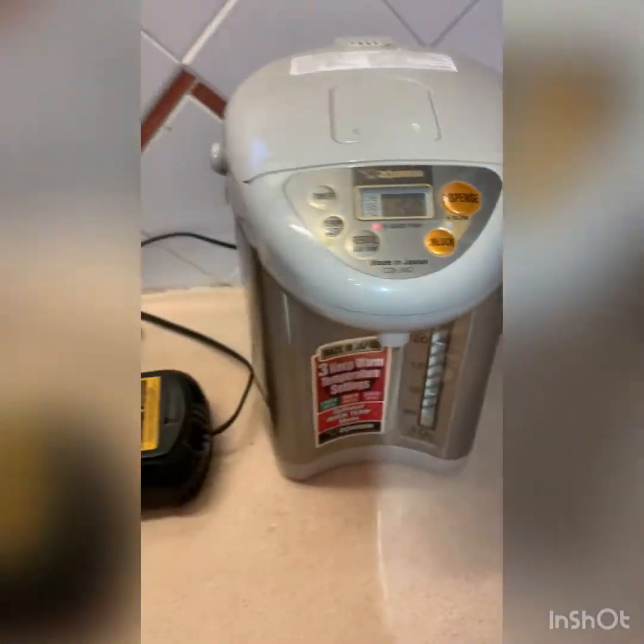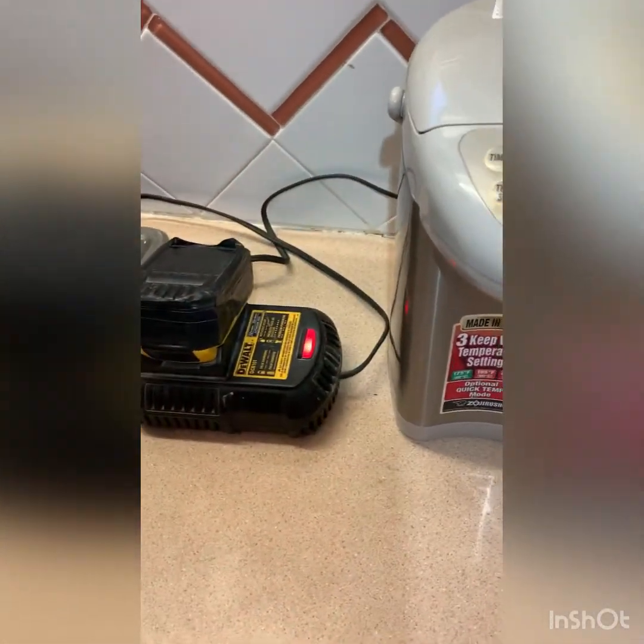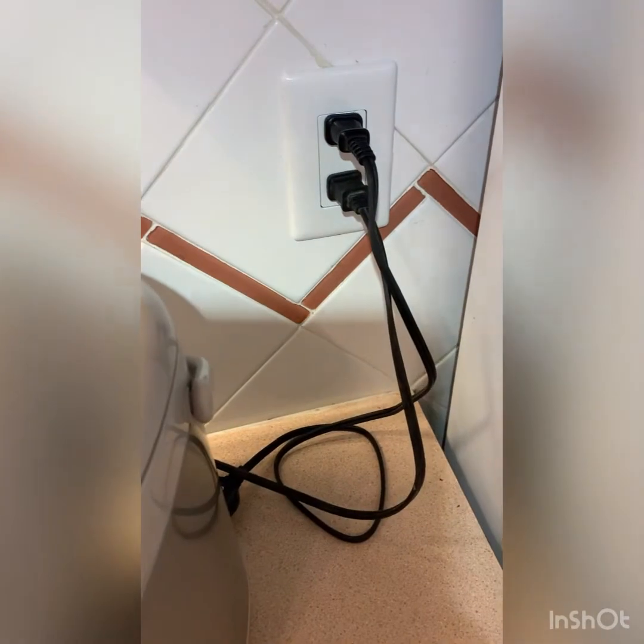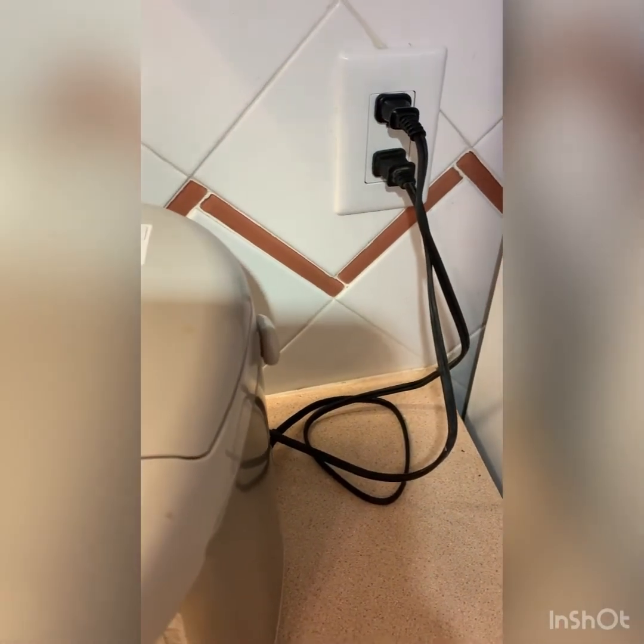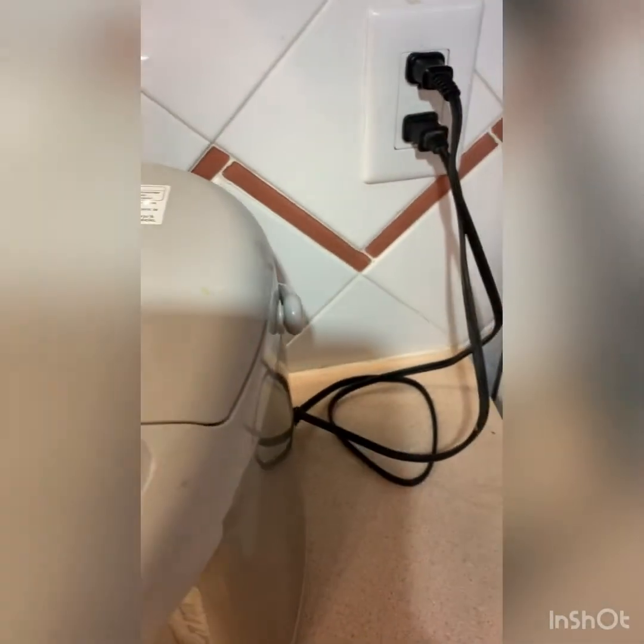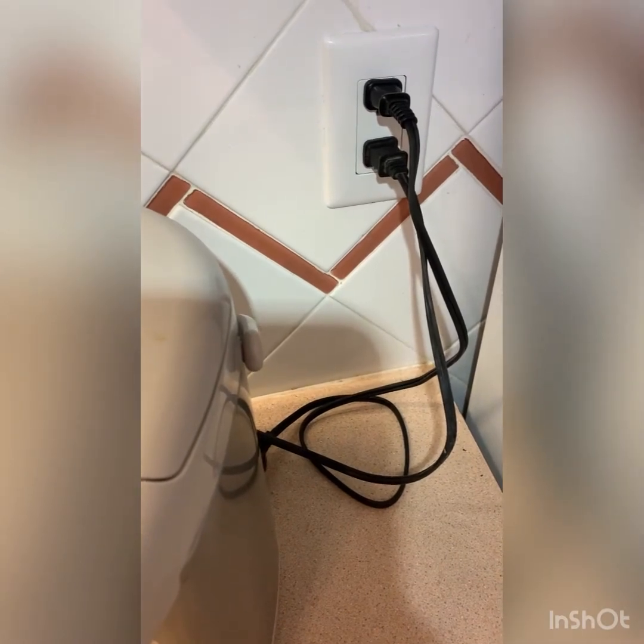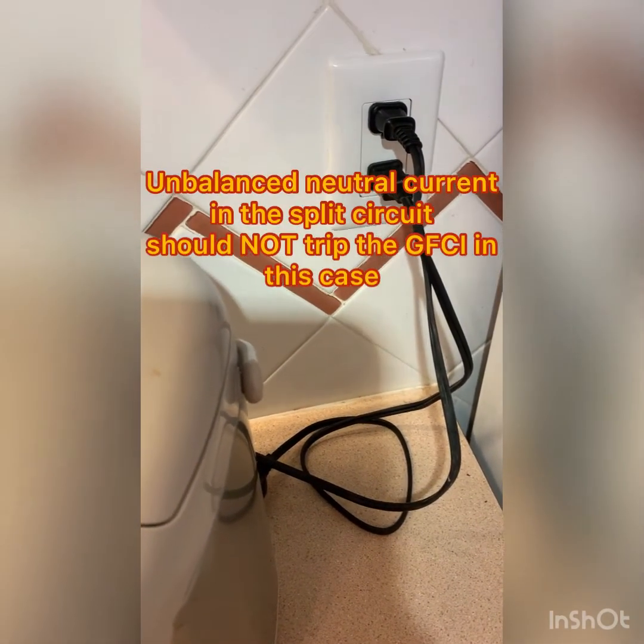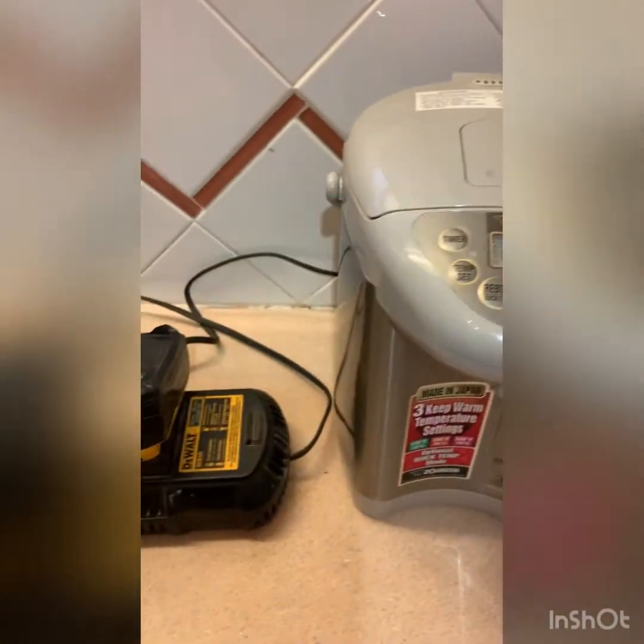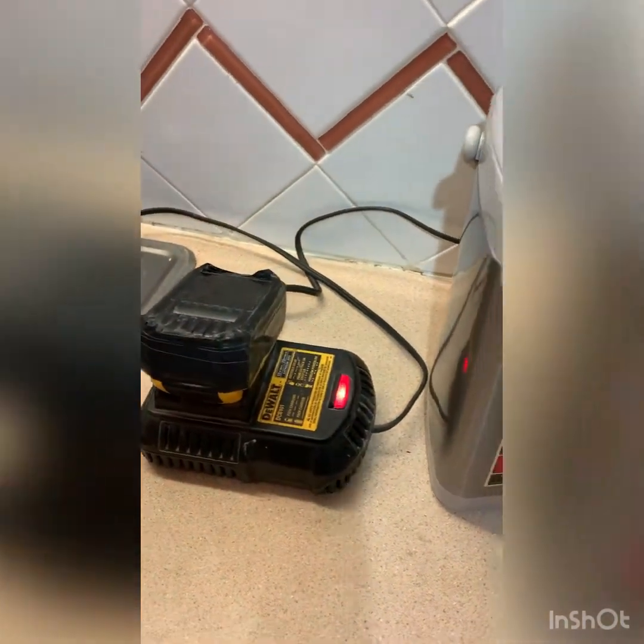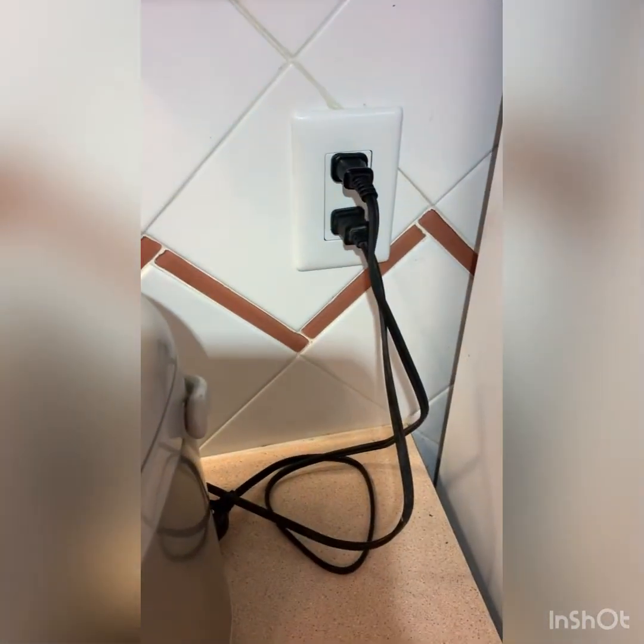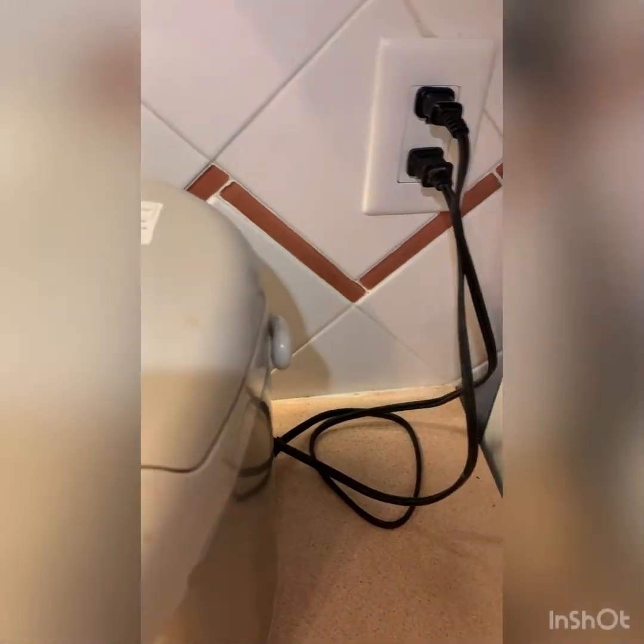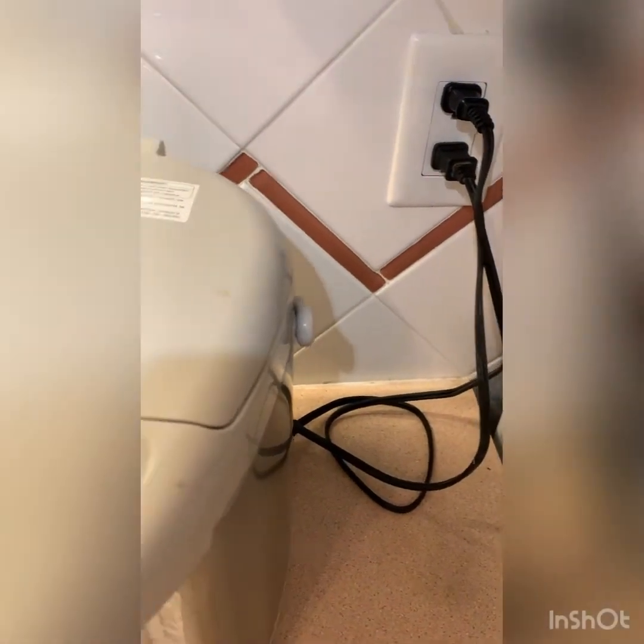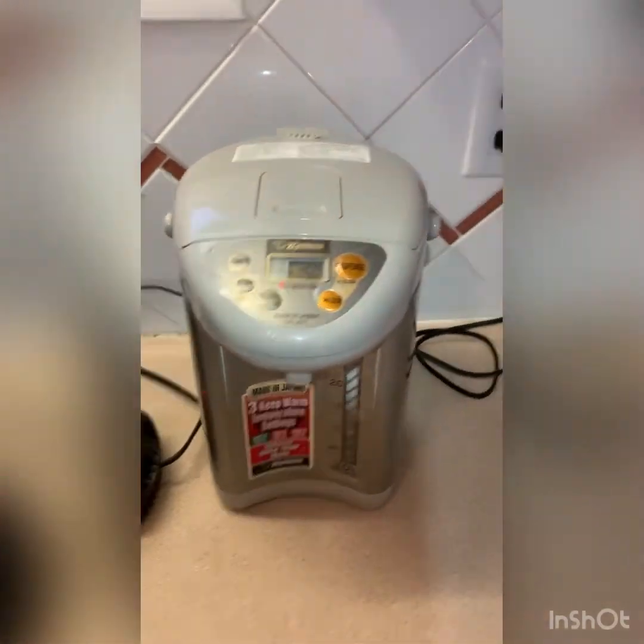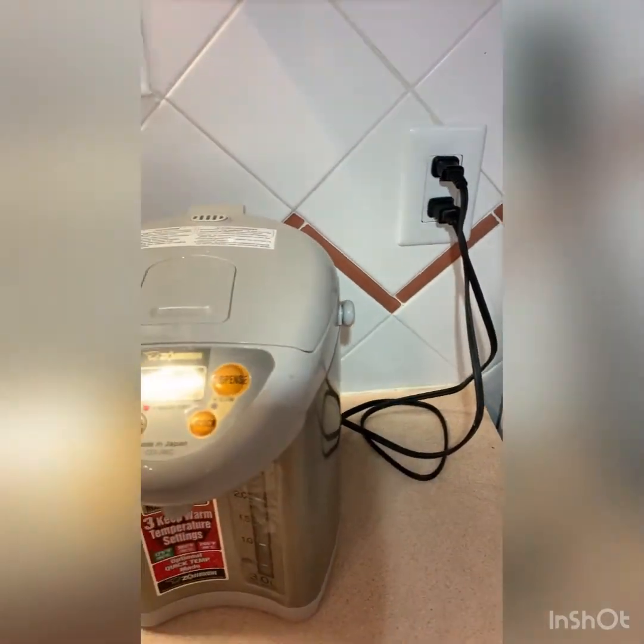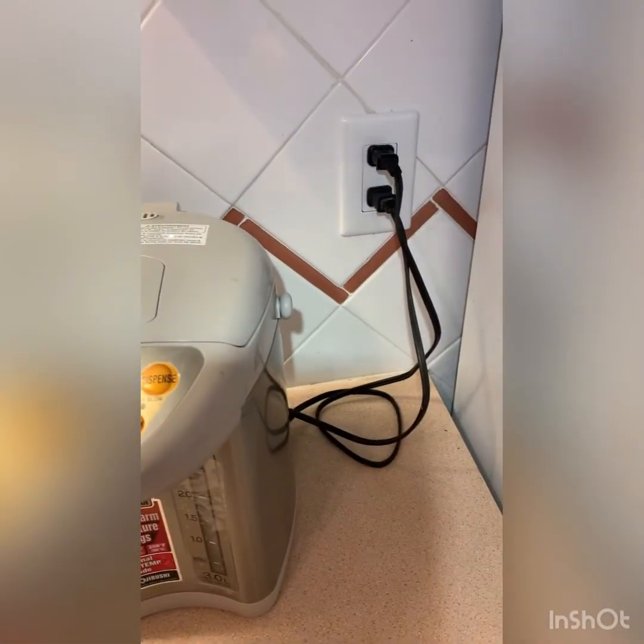The reason I have to test it this way is because this is a split receptacle. I want to create an unbalanced neutral current in the neutral wire to see if it will suddenly trip the GFCI. I don't know if you understand, but simply it's just for testing. It works—no trips for normal use.